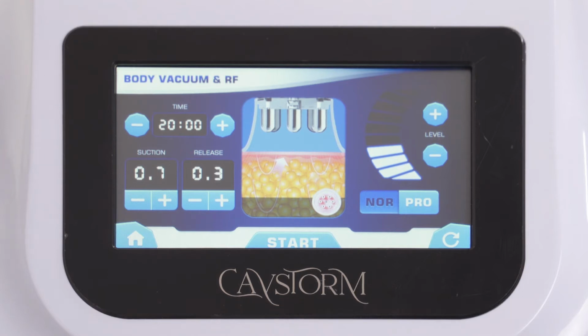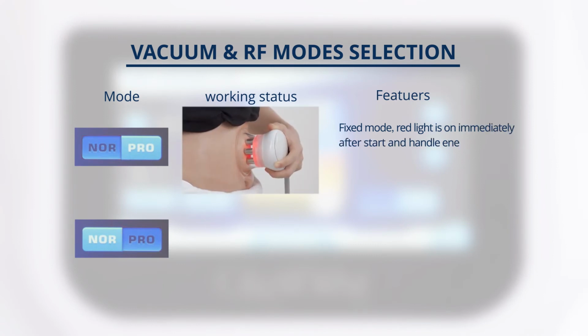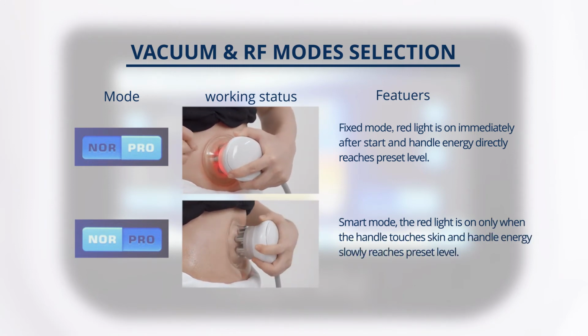Mode selection, normal mode. After pressing start button, handle energy directly reaches preset level. Pro mode. After the handle touches skin, handle energy slowly reaches preset level.